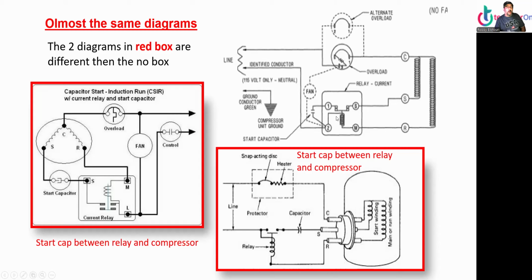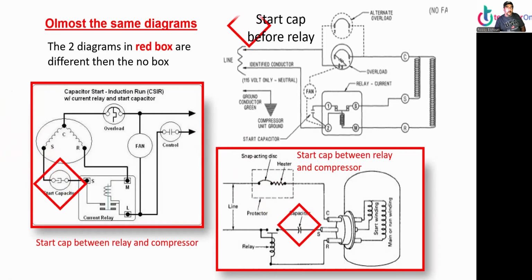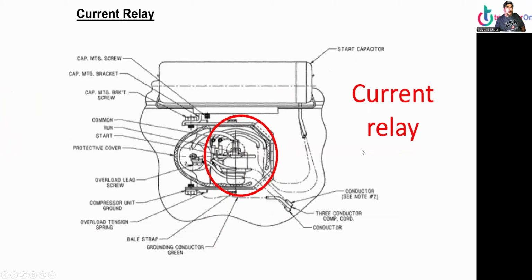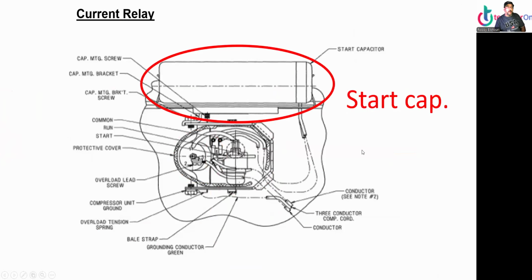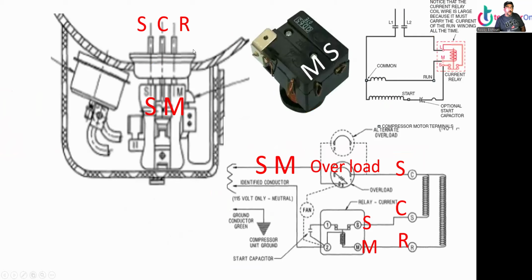I have the wrong one. Yeah, correct. That one on top is the one, no box, start capacitor, different location, but it works the same way. All right, and this one, start capacitor before the relay. All right, now current relay, overload, and capacitor. So current relay, common start, common and run of the compressor, and S and M. Okay, S and M overload, start, common, run. This is that picture. Let's move on.